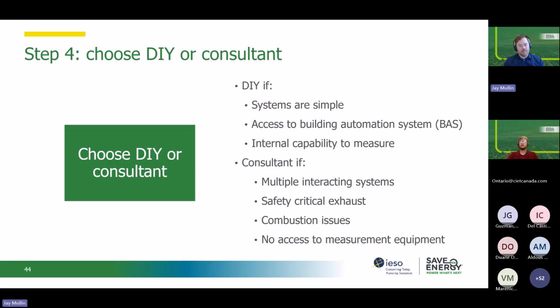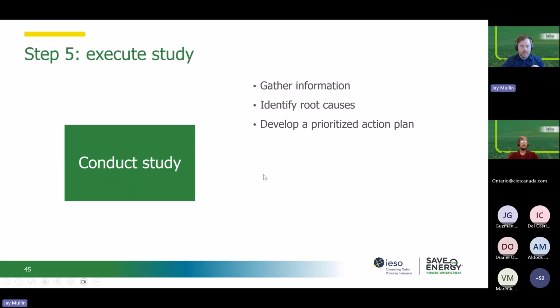We often see organizations engaging a consultant if their systems are more complex. So if there's multiple interacting systems or equipment, if like safety critical exhaust is important, or if there's combustion issues. So once those health and safety risks start popping up, you may want to get the knowledgeable consultant in to make sure that those are being addressed properly. Or also if they just don't have access to measurement equipment or those internal capabilities to do this kind of work. And then the execute study, which we covered in detail earlier: gather information, identify root causes, develop an action plan.